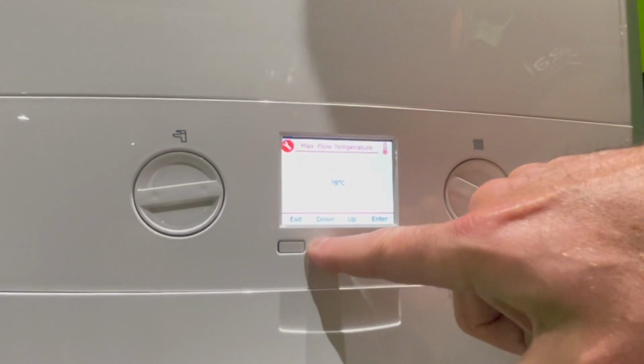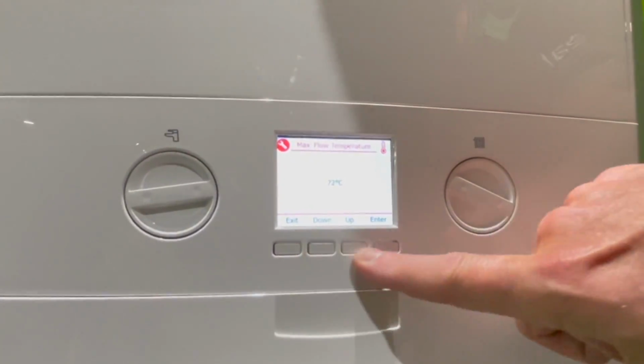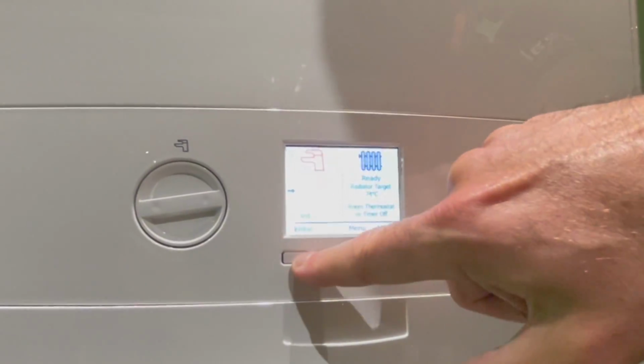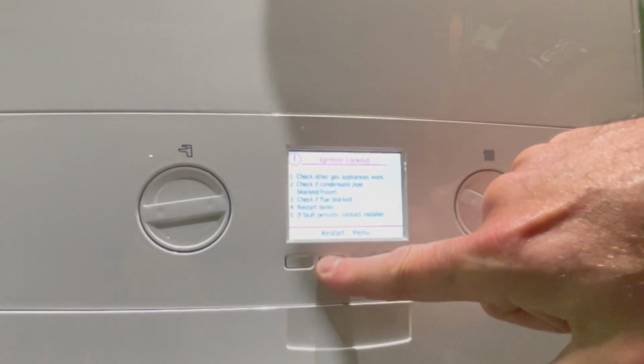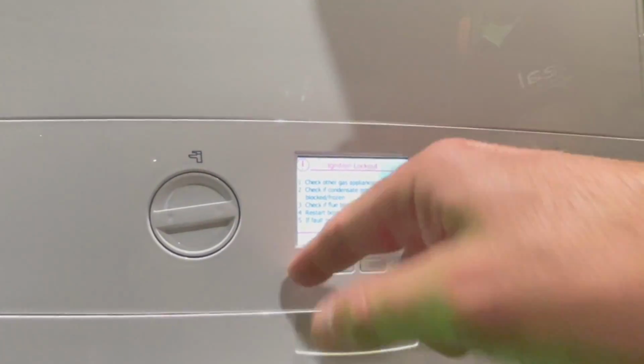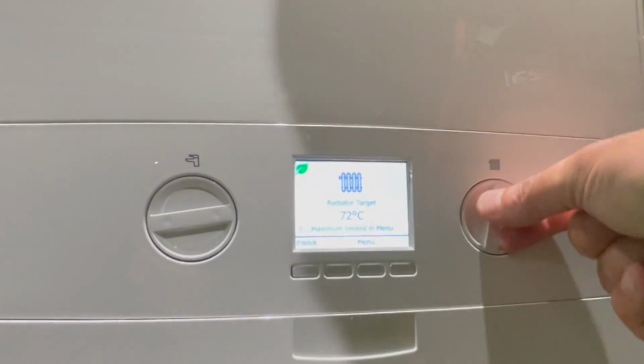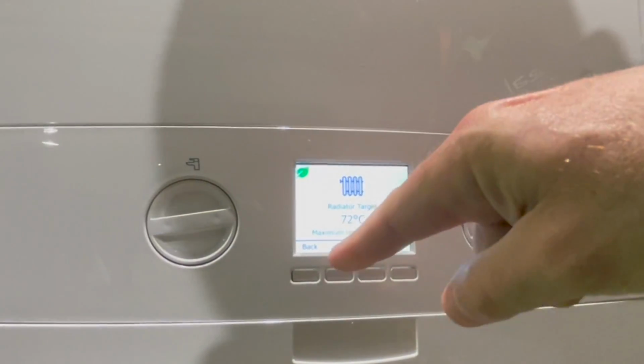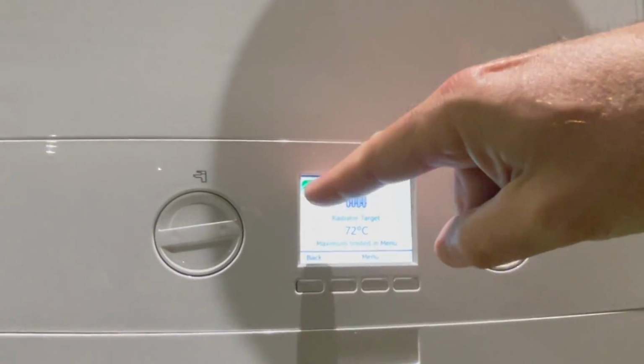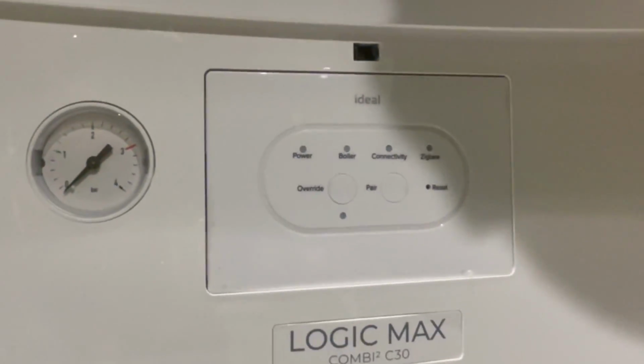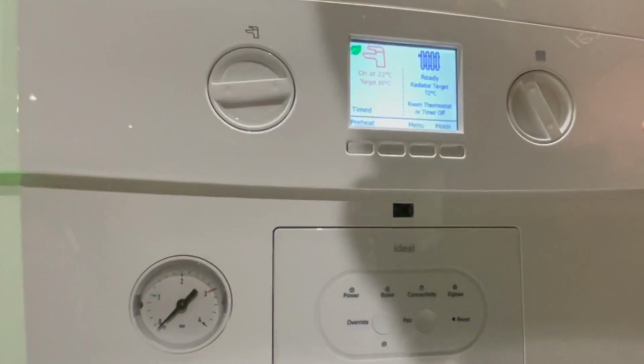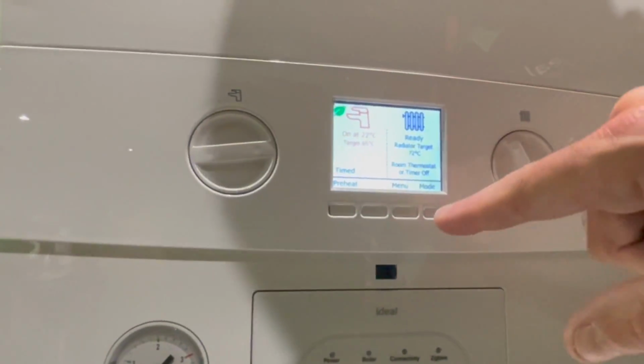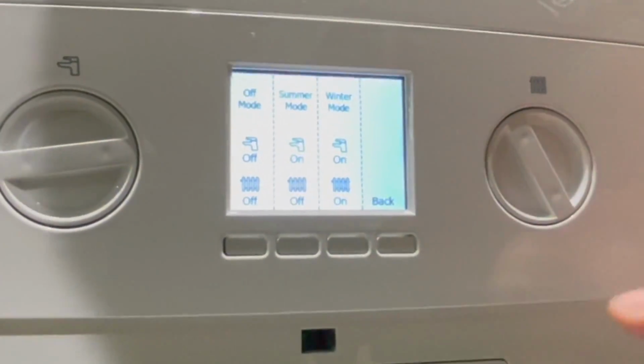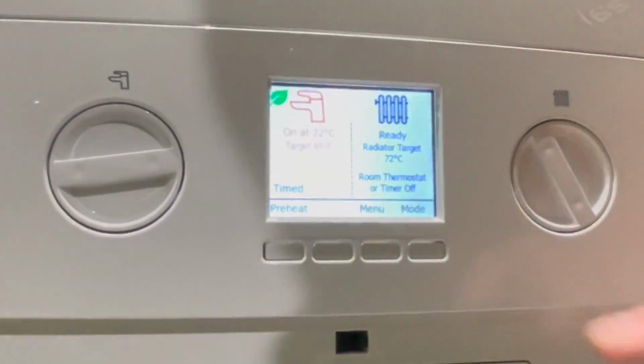Another new setting they've got is to stop the maximum flow temperature being altered by the customer. So you could set it to your 55 degrees like you're supposed to do now, and no matter what the customer does when they turn the knobs, it won't change the temperature. I guess you've noticed there's no pressure gauge there now, so if we press the flap down, it's been moved behind the flap. And because there's only 2 knobs now, the on-off winter-summer is now a smart key.